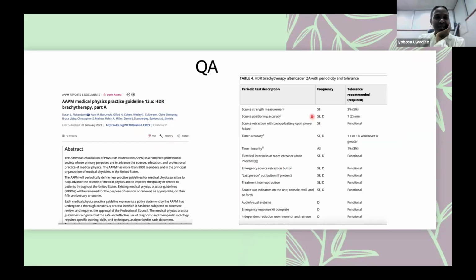It's quite tiny. Well, okay, I can see. Source strength measurement, of course, which we do. The recommendation here is to do it at source exchange. We use a cobalt source, so that means once in about 6-7 years. But we do it regularly, maybe twice a year, or for teaching purposes, so we do it more frequently than what is recommended. Of course, those who use iridium will be doing it 4 times a year. Then, of course, the source positioning test, which we do daily.